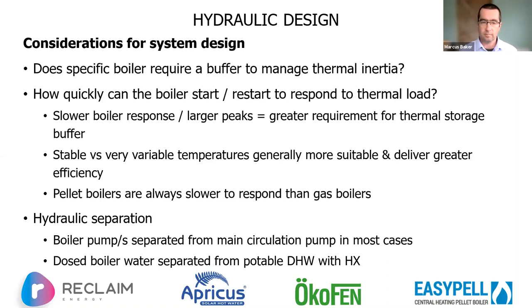And how variable are the temperatures, and therefore the size of the buffering, and whether we're getting into the right efficiency point. Just bear in mind that they're always slower than gas boilers. We're always going to have some degree of hydraulic separation so that the boiler pumps are not being driven by the main circulation pump. It may be a case that the boiler pump can do it, but it's unlikely in a commercial context.